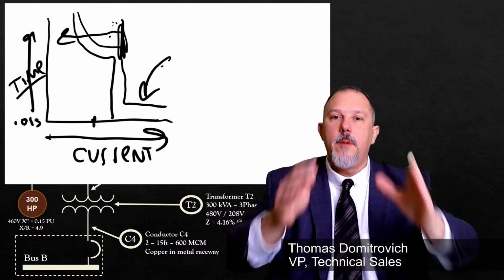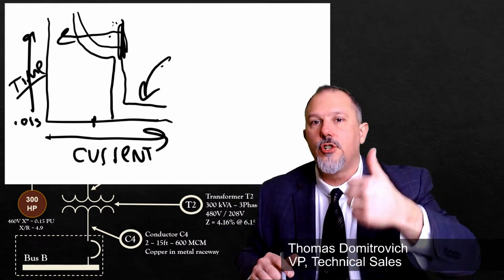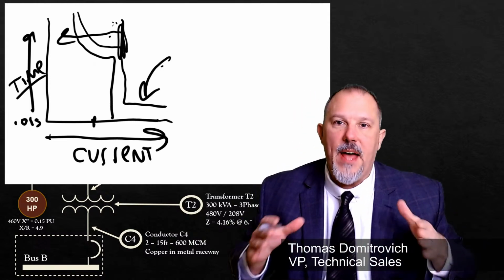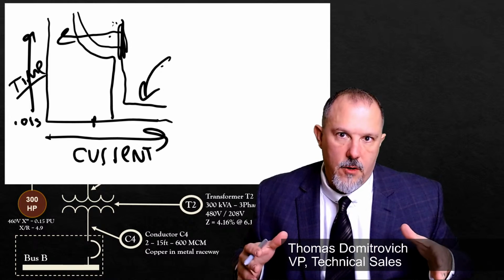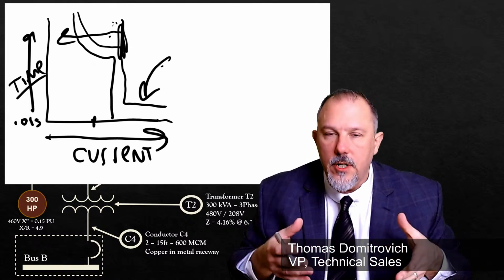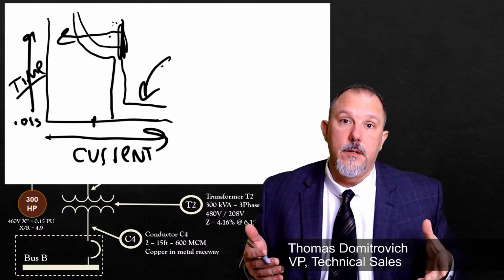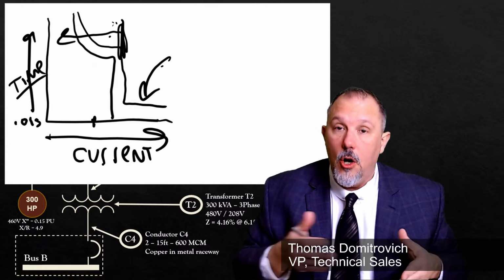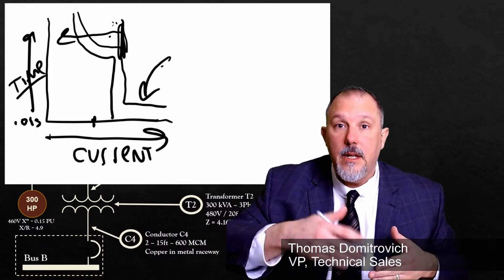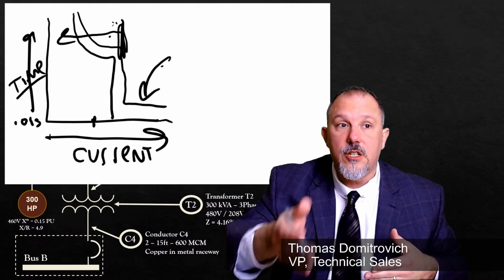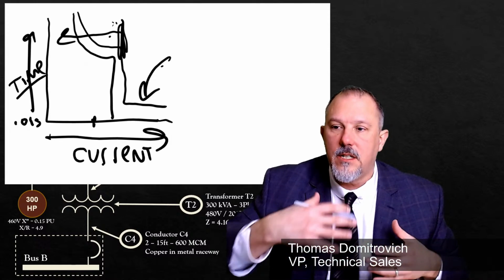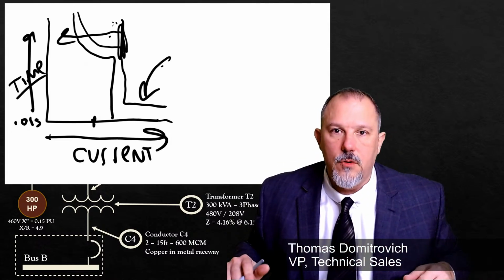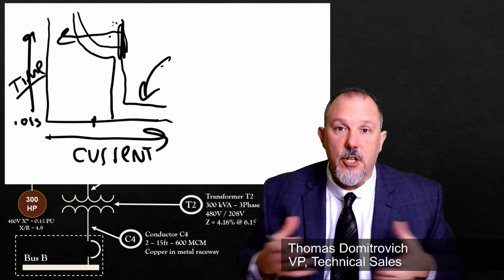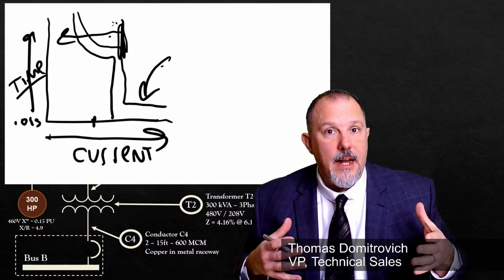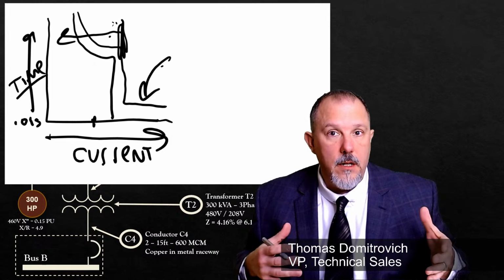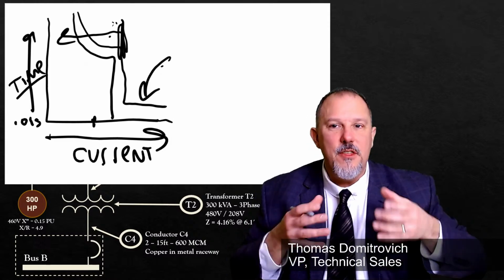Remember, what's the difference between a short circuit and an overload? A short circuit goes outside the path that it's supposed to travel on. An overload stays in the path. A good example of an overload is motor inrush current. Motor inrush current is a temporary overload, an overcurrent in the system. It's a lower current, not a very high fault current, because you're still impeded by the resistance and impedance of the circuit, because all your currents are in the path.